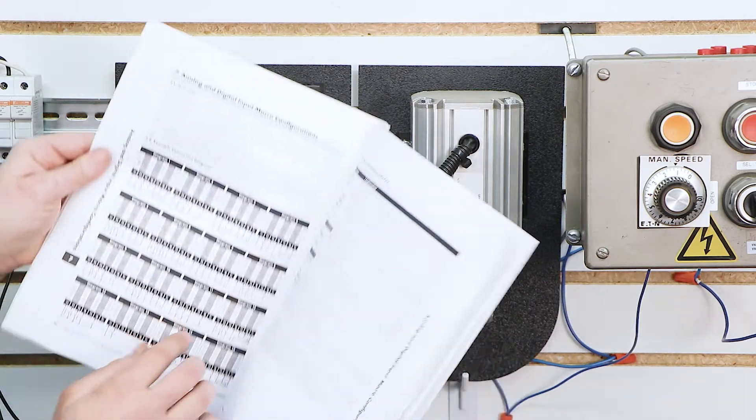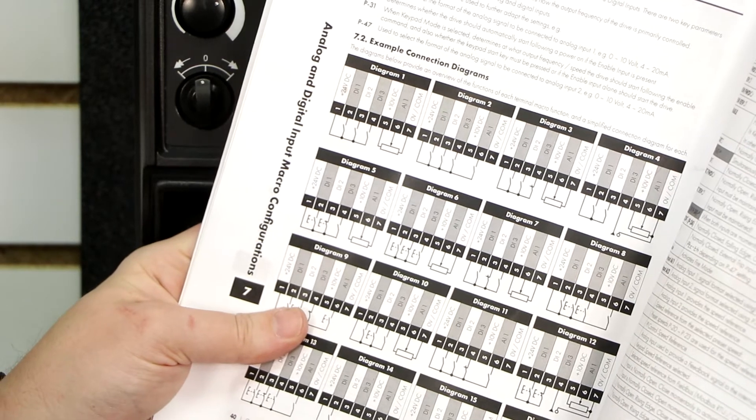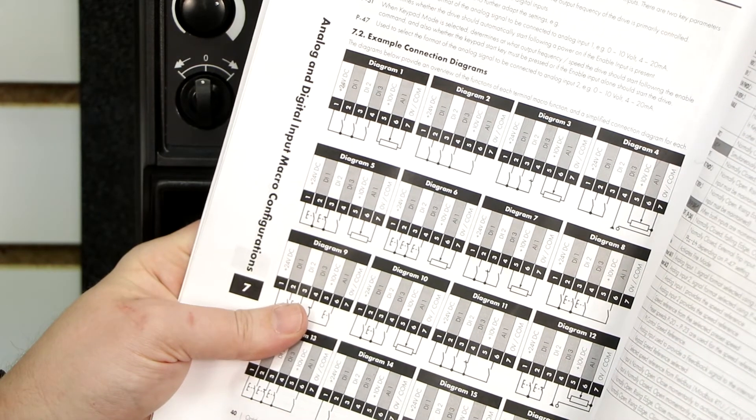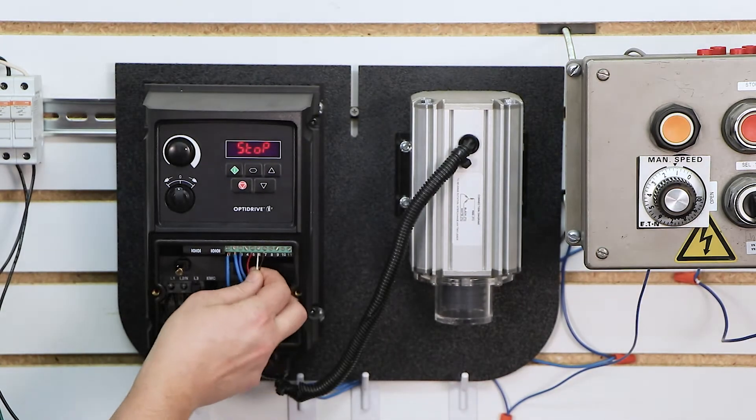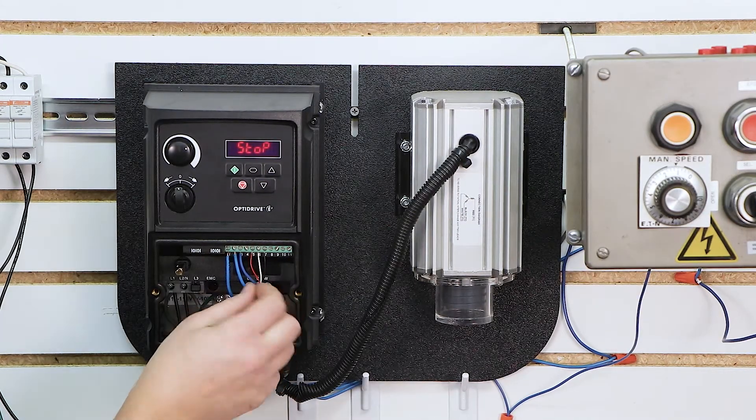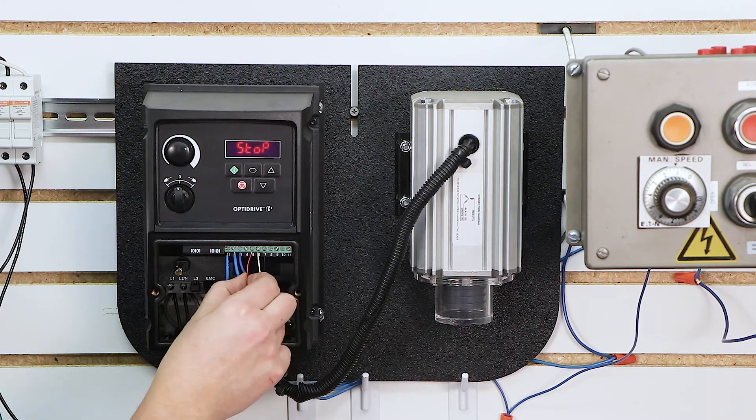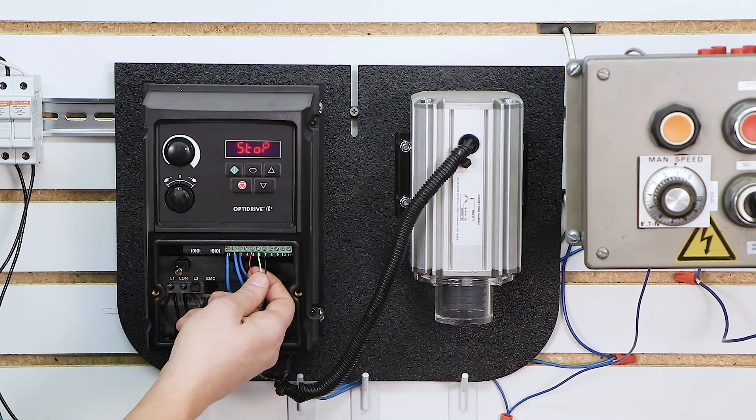Lastly, we can look at our analog input wiring here. 5 is plus 10 volts on our speed pot. 6 is our analog reference or analog input from the speed pot. And 7 is our common on our speed pot. You'll probably need to look at the back of your speed pot to match those. These colors may not match exactly what yours is. But for mine, my plus 10 volts on my pot was red, my signal was white, and my common was black. So that's what I wired to those.